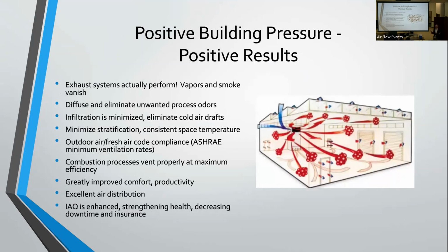People find solutions on their own, and usually it's just a matter of putting a louver in the wall to help relieve that negative pressure, but that's not the best fix. The best fix is applying makeup air to positively pressurize that space. What is that doing? That's now allowing those exhaust systems that you just put in place to actually breathe and pull that air out of the building like they're supposed to.